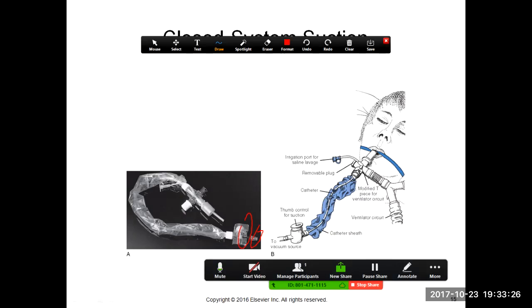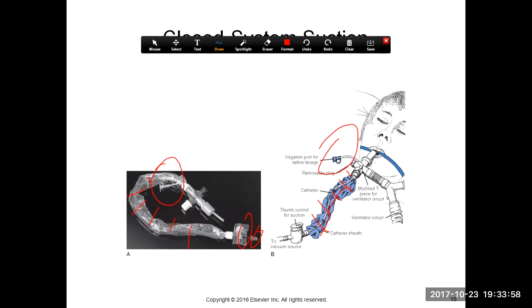There are typically numbers up and down here, and so you see this gentleman here, we have the sheath that covers that, and numbers that tell us our depth, so we can match the numbers with the ET tube and make sure we're not going too far beyond the end of the ET tube. This little device here and here, that's for instilling saline. We really don't lavage a whole lot. We shouldn't. The data shows we're washing surfactant out of the lung and causing ARDS. So the only time we're really going to flush a lot of saline down there is if we have mucus plugs and dry secretions, and at that point we should go to a heated humidified circuit.